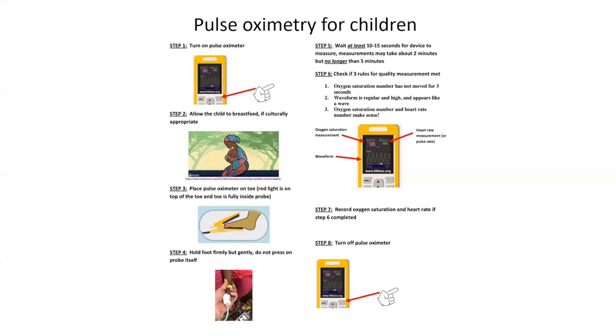And just to add on to that, we also recommend holding the extremity gently but firmly during the measurement. So it's not something in which you put the probe on the child and then your hands are off. Usually we find that the child then starts moving and is interested in what's on their toe or finger. And so having a gentle but firm hold, not pressing the pulse oximeter, can reduce some of that movement artifact and make it easier to get the measurement.